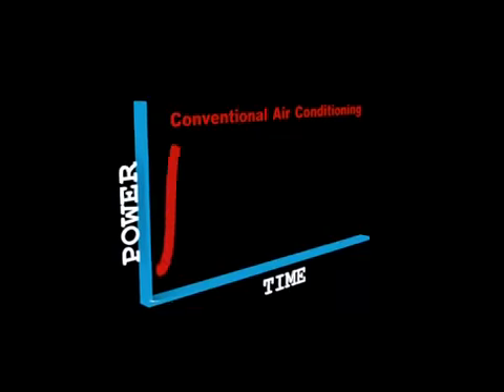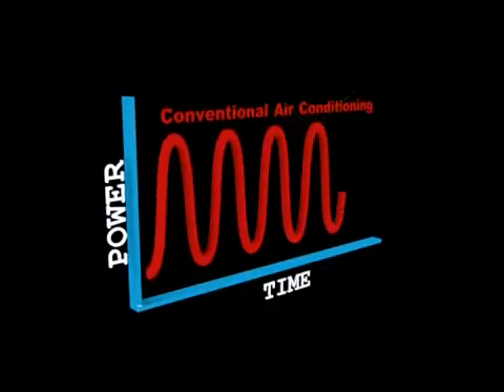Older cooling systems rely on thermostats to control room temperature. With this method, your cooling unit is either running at full power or completely shut down, often shuddering to a noisy stop. The result is inconsistent room temperatures and a huge waste of energy.